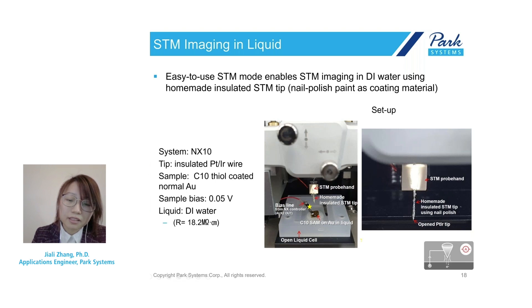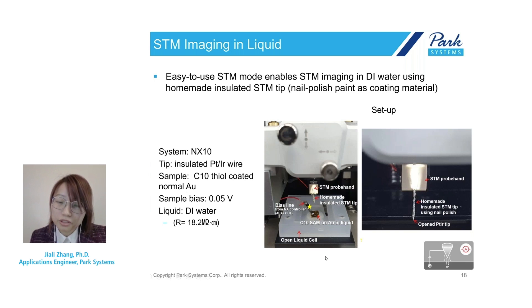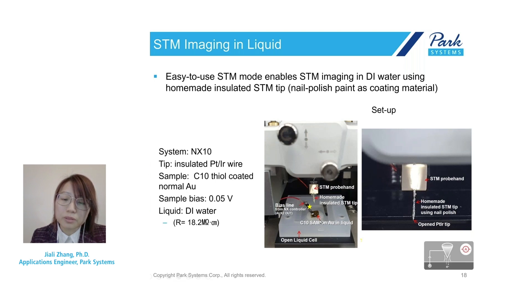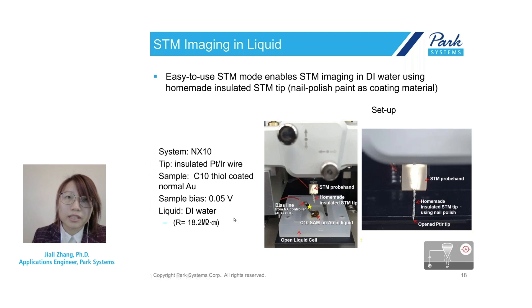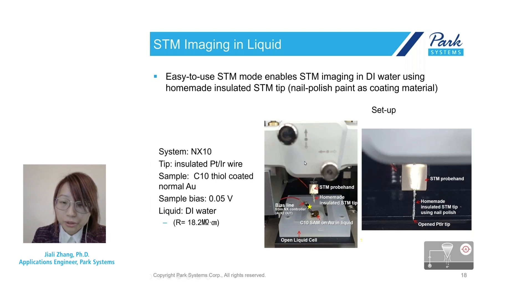Since this is liquid imaging, we utilize a liquid cell. For most researchers, you can use your own liquid cell or a Petri dish, but make sure the sample is well mounted — here we use a clip that is also insulated with nail polish. The sample used is C10-thiol-coated gold created by thermal evaporation, and the liquid is DI water. All other setup is similar: we still connect to the internal current amplifier and use the STM probe head.